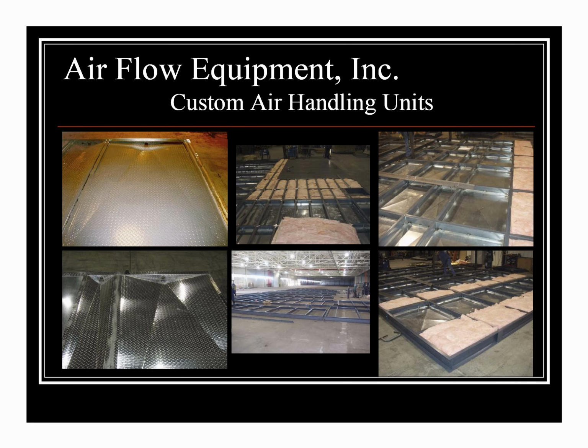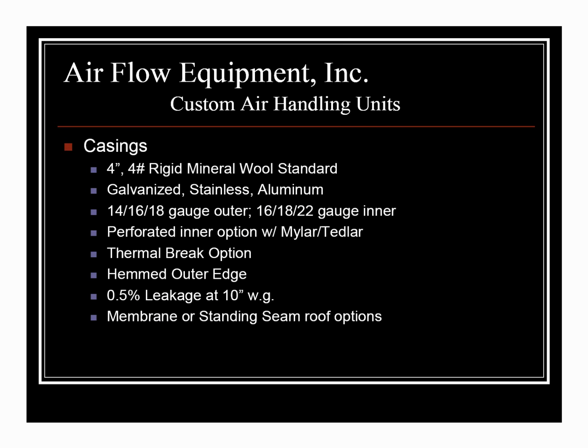I have one example where we did that. We put a 30,000 CFM rooftop unit with a service corridor over an operating room at a medical center in Traverse City, Michigan. As we developed that unit, it was repeated again and again that sound was critical, especially radiated noise through the base, since you're above an operating room with surgeons who like things quiet. And they have a lot of pull in the hospital, so there was a lot of concern.